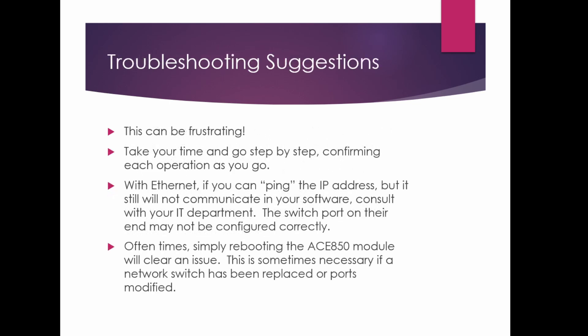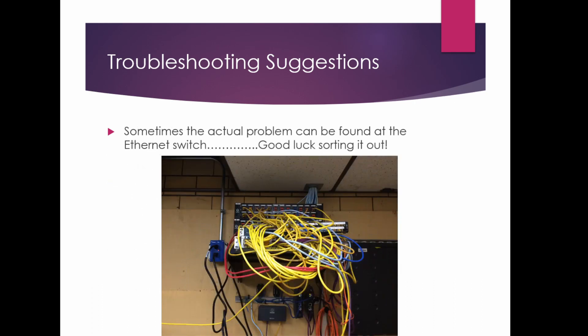Some suggestions: this can be frustrating, so take your time and go step by step, confirming each operation as you go. Most of the time with Ethernet, if you can ping the IP address but it won't communicate, consult with your IT department — the port may not be configured properly or could be on the wrong VLAN. A lot of times simply rebooting the ACE module will clear the issue, especially if a network switch has been replaced or IT has been changing port settings.